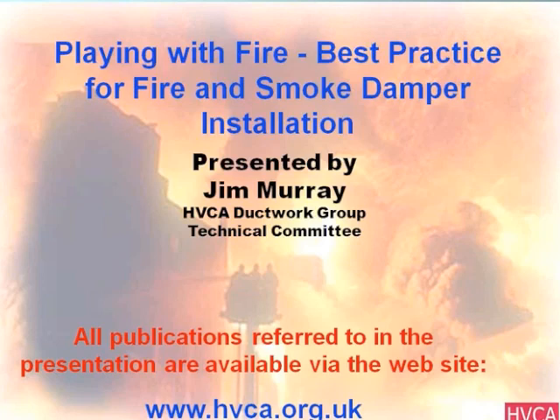I am very interested about support details for fire dampers installed within flexible ceiling void fire barriers - requirements of support type and size of supports available, certification, etc. As far as I know, there is no manufacturer who did testing in reality, just BRE assessment. Is this correct, and with the introduction of new BSEN 15650, will testing be mandatory with no assessment possible to BS 476? And finally, is gripple wire use possible for fire damper installation? Are there any tests for this application? I presume just fire test data for gripple wire is not sufficient enough.